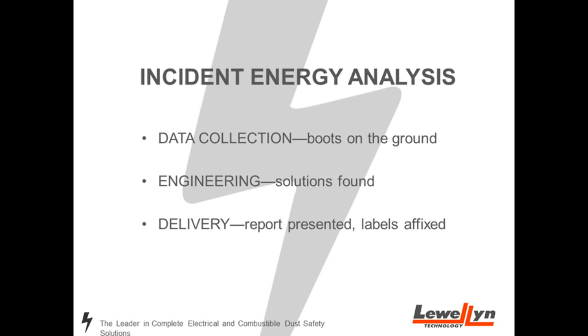But there are 3 main steps. First, data collection. Someone has to be in your facility in order for you to have an incident energy analysis done. Someone has to break a sweat, someone has to be in the building opening up electrical equipment. If you're talking to firms that say, send me your electrical drawings and we'll send you some labels - no. Hide your checkbook and run away. You can't do it that way.